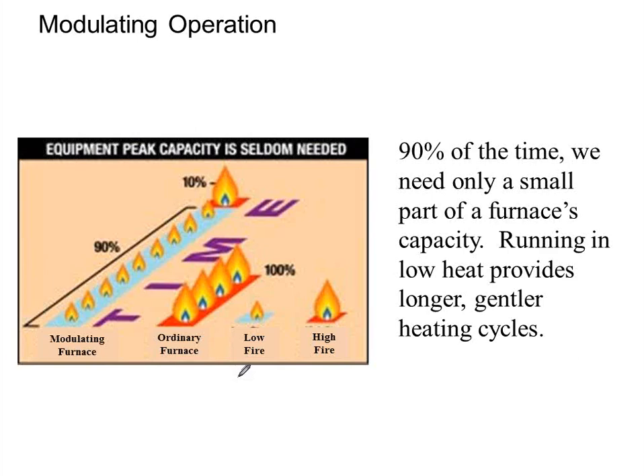Wouldn't it be great, Mr. Homeowner, if I could give you two furnaces, one size for the mild days of the year, one size for the really cold days of the year. So instead of having my full flame on for a short amount of time, I could have my little furnace running for most of the year, 90% in this case, and then every once in a while when it's -4, 10 degrees outside, something like that, I got to bring the big furnace on. The modulating furnace does the exact same thing, except it's like having 60 little mini furnaces, each one sized for a different day of the year, plus the big furnace designed for the -4 degree day outside.